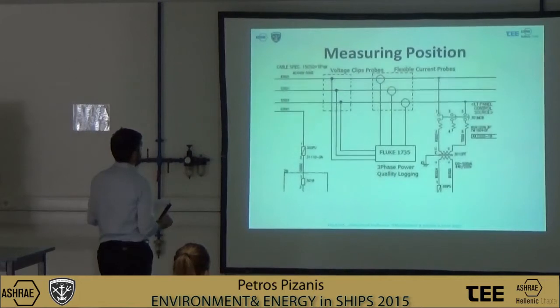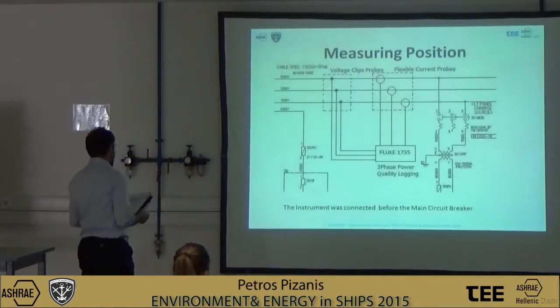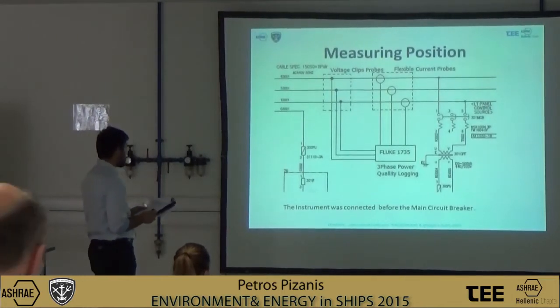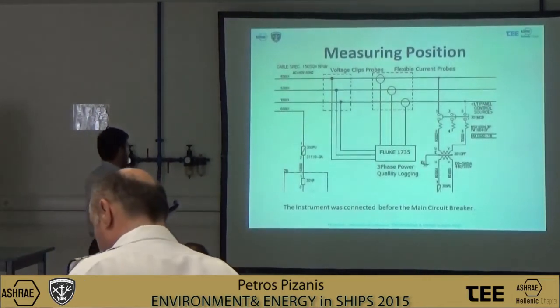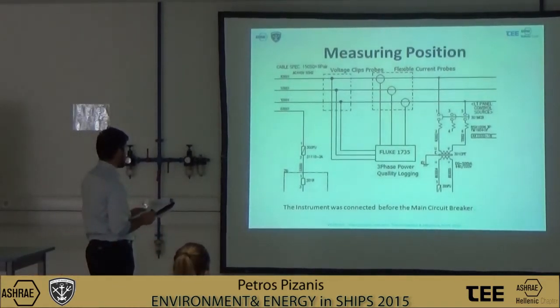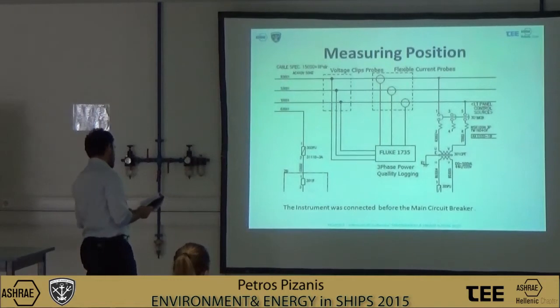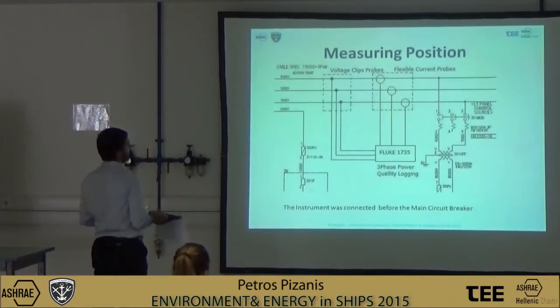The logger is connected to the main supply of the QC crane, after the transformer and on the low voltage coil, in order to have a complete insight as to what consumption was being used on the crane and to be able to find the maximum distortion of the whole crane. The logger is connected as stated in its operating manual.